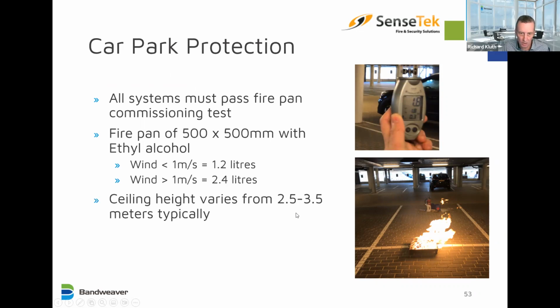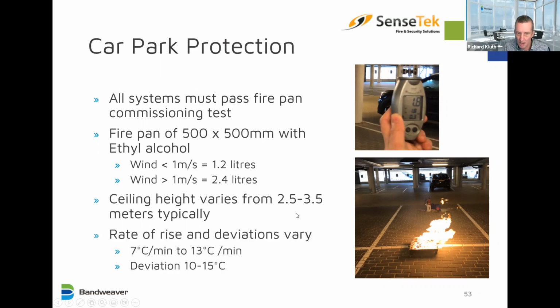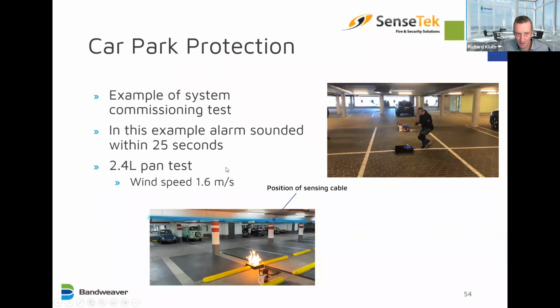Ceiling height is typically 2.5 to 3.5 meters. Normally, the rate of rise deviation is either 7 to 13 degrees C per minute or 10 to 15 degrees deviation. We'll look at a video of a test here. In this example, it sounds within 25 seconds. We'll see the wind speed is high, so it's a 2.4 litre test. You can see the fire pan here, you can see the cable here. It's installed at this point here.